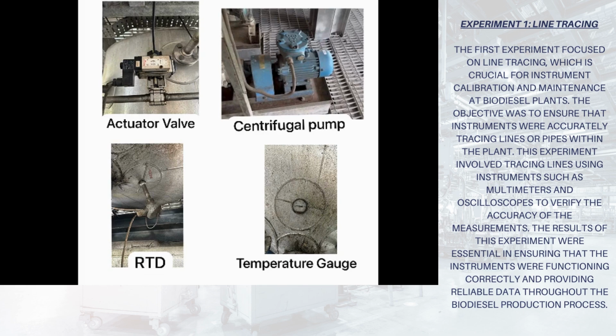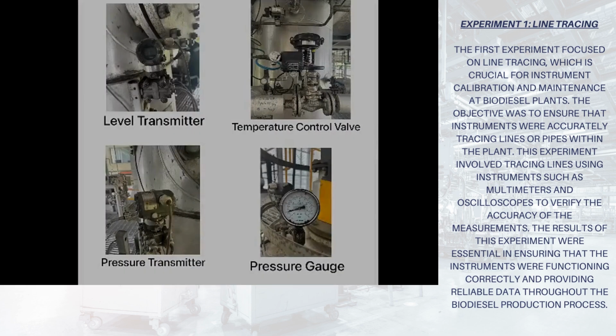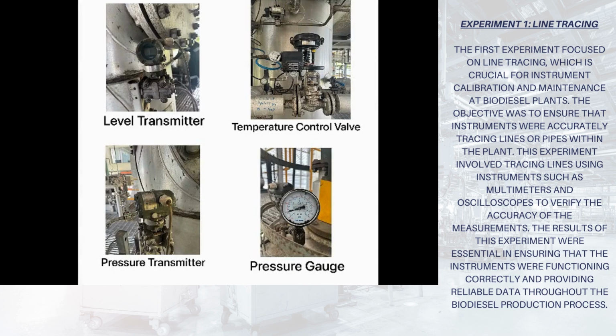moves materials through the system, a level transmitter that measures material level in tanks, a temperature control valve that regulates temperature within the system, a pressure transmitter that measures system pressure, and lastly, a pressure gauge that provides visual pressure indication.